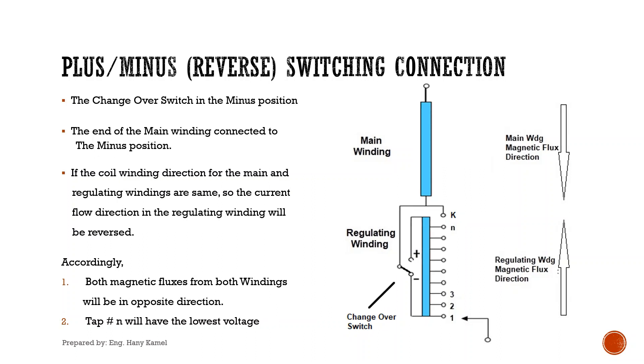But if the changeover switch is in the minus position, the end of the main winding is connected to the minus position. If the coil winding direction for the main and regulating windings are the same, the current flow direction in the regulating winding will be reversed. Accordingly, both magnetic fluxes from both windings will be in opposite directions. In this case, tap number N will have the lowest voltage.